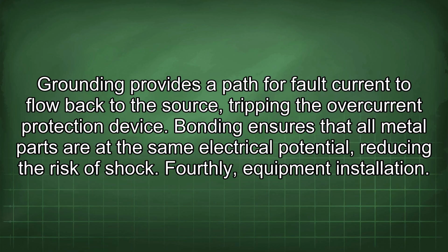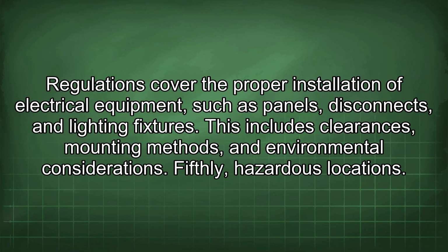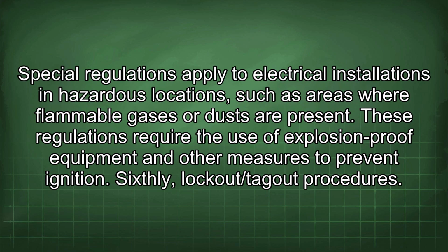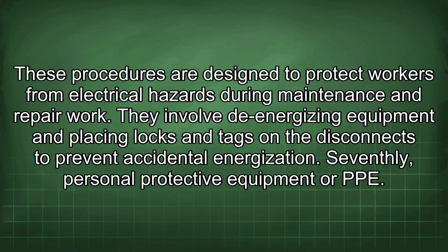Fourthly, equipment installation. Regulations cover the proper installation of electrical equipment, such as panels, disconnects, and lighting fixtures. This includes clearances, mounting methods, and environmental considerations. Fifthly, hazardous locations. Special regulations apply to electrical installations in hazardous locations, such as areas where flammable gases or dust are present. These regulations require the use of explosion-proof equipment and other measures to prevent ignition. Sixthly, lockout/tagout procedures. These procedures are designed to protect workers from electrical hazards during maintenance and repair work. They involve de-energizing equipment and placing locks and tags on the disconnects to prevent accidental energization.